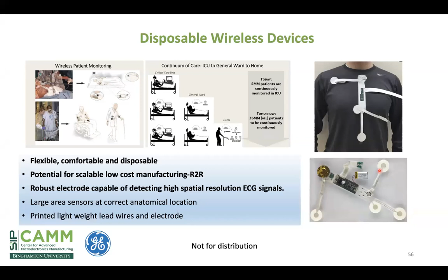Involving screen printing, and then involving lamination, because ultimately we needed to make a multi-layer structure for our cable that resisted the triboelectric effects causing static and noise. And so this had to be a multi-set of materials and multiple inks, things that had to be laminated together, and of course tested to show that they would in fact work, leading to our ability to have this truly multi-point type analysis of respiration, core body temperature, reflective SpO2, oxygen sensing, and a 3-lead ECG, all in one device.